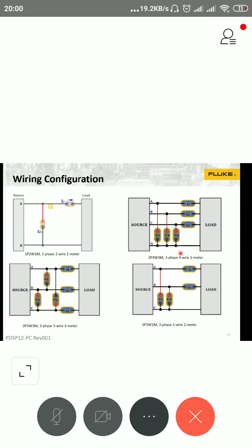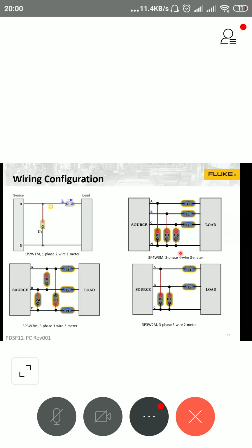In configurations, generally it can be used for single phase as well as three-phase configurations. In three-phase we have star and delta systems, so we call them the three-phase four-wire method and the three-phase three-wire method. So you can use the product for any of these applications. And not only that, a 2-watt meter method can also be used with this device to do the measurement. So here the interesting part is you can choose the configurations and select, then connect the connections, because the channels are isolated. So you can connect AC and DC also, and you can do the measurements.